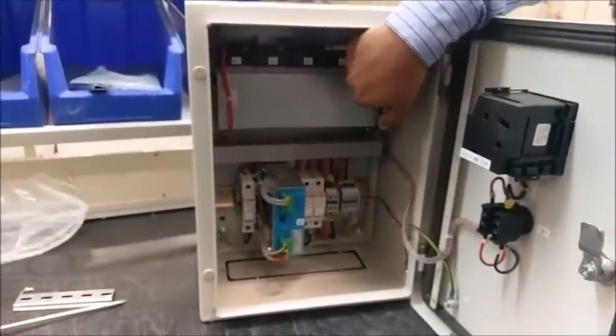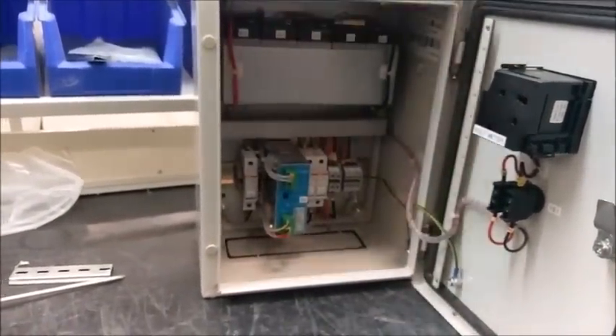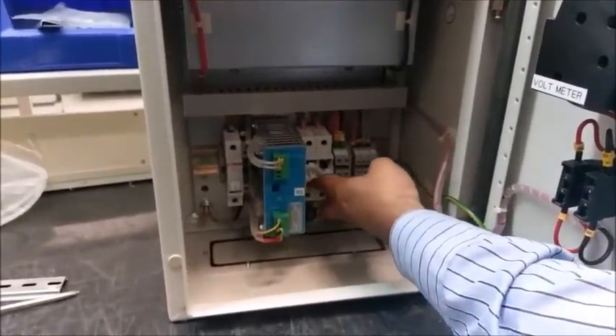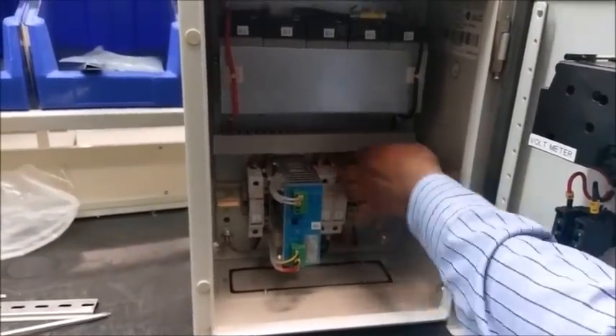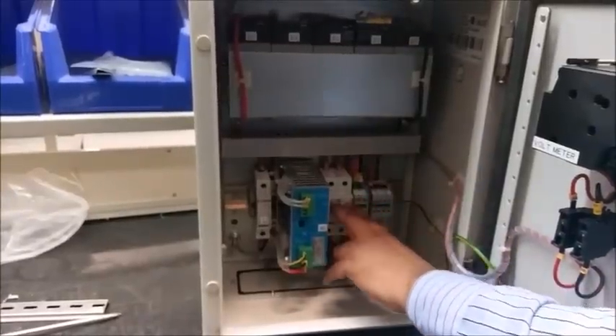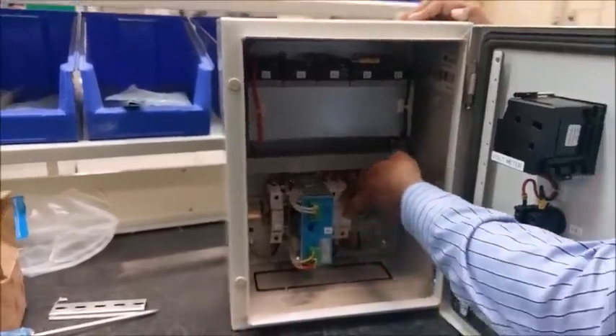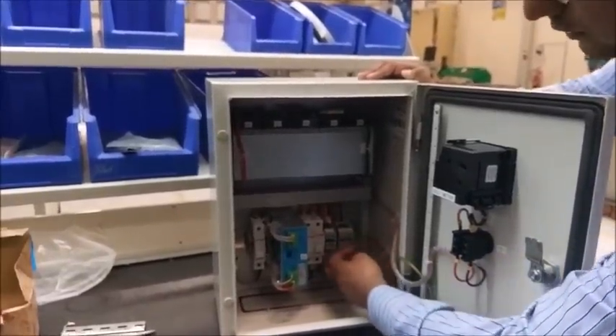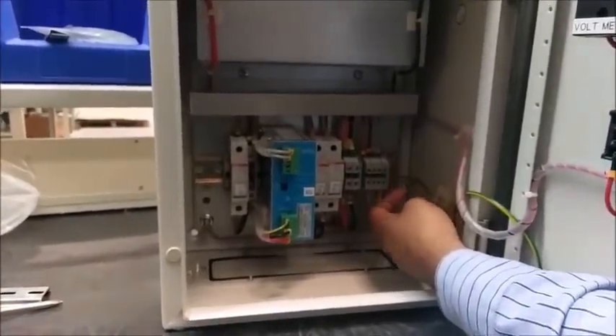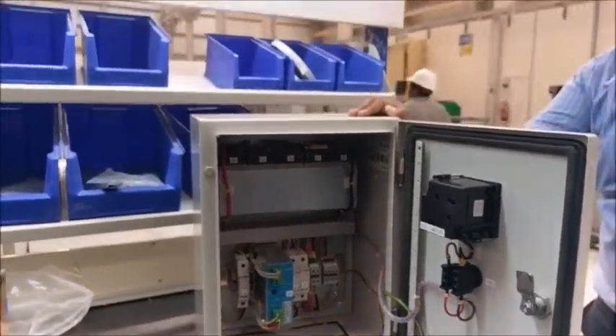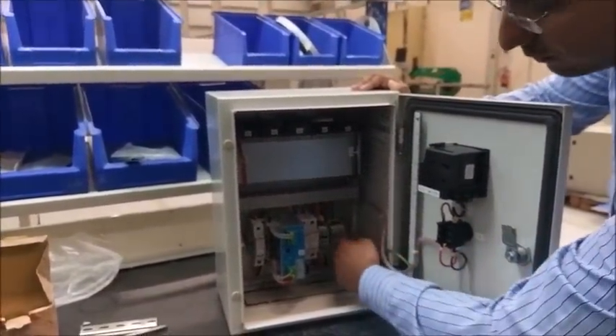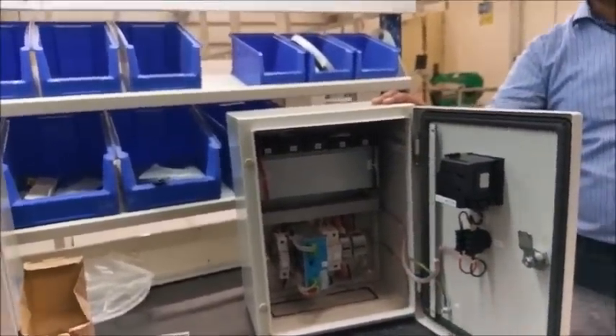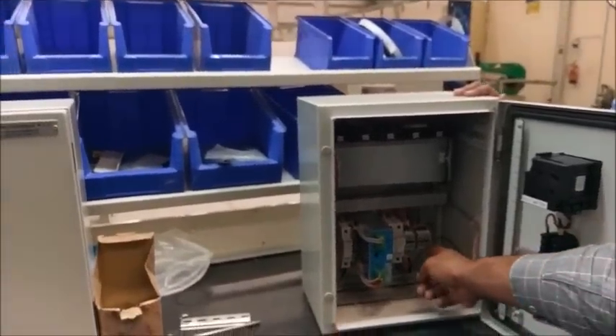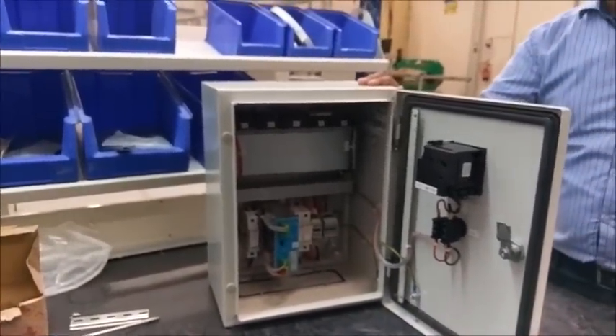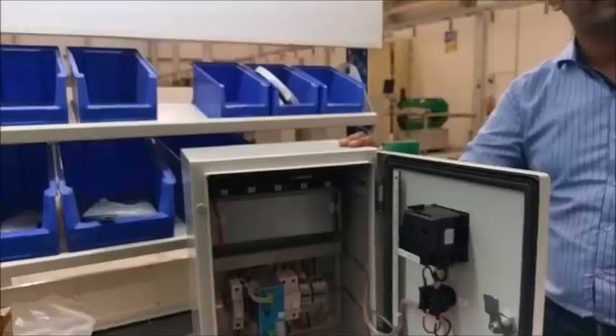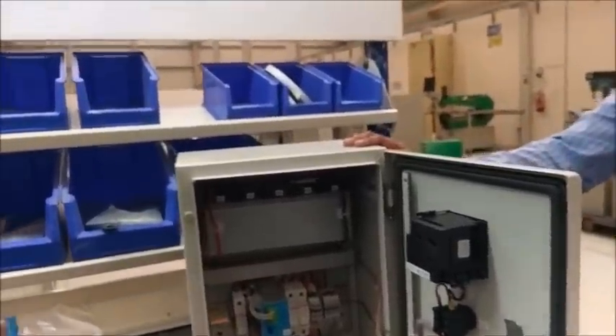These are there, and the battery charger is there. For that protection, these fuses are also there. Fuses, and this will be 4 ampere. And here, the terminal boxes are there. From this terminal outgoing side, this wire will go to the LV panel tripping coil. No, this is not a relay. That is a terminal block.